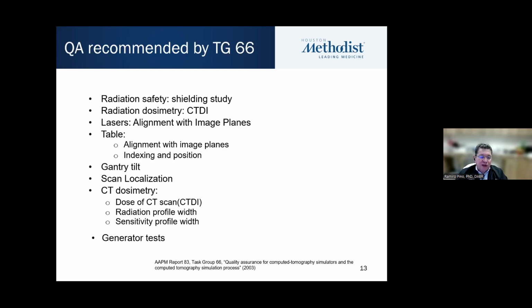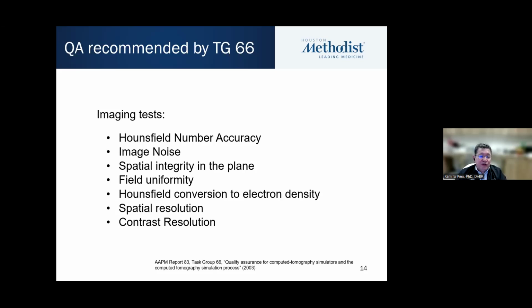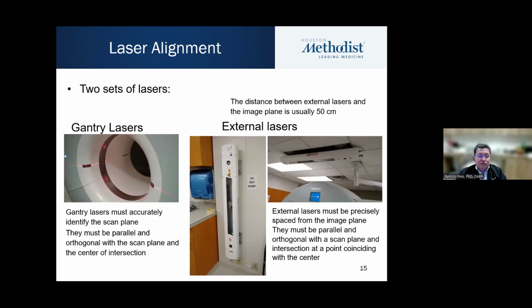We need to check for gantry tilt, scan localization, CT dosimetry in general, radiation profile, sensitivity profile, and generator tests. In imaging tests, we typically look for Hounsfield number accuracy, image noise, spatial integrity, field uniformity, the conversion table from Hounsfield units to electron density, spatial resolution, and contrast resolution. So typically in the simulator, we have two sets of lasers. We have the ones that are in the gantry, internal lasers, and typically we have external lasers as well.